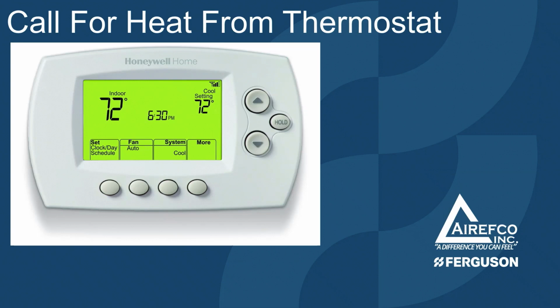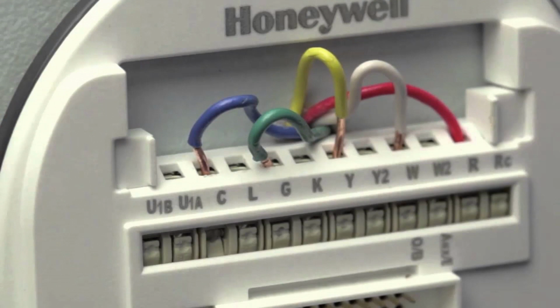So the first thing that's going to happen is the thermostat is going to call for heat. And you need to be able to check out the thermostat if this doesn't work. The best way to do that is take a voltmeter, and we're going to check between R and W to see if the thermostat is calling for heat. If you remember your NATE certification test or your basic electrical class, you will remember that when a switch is open, you will have 24 volts. When a switch closes, you will not have voltage across that switch.